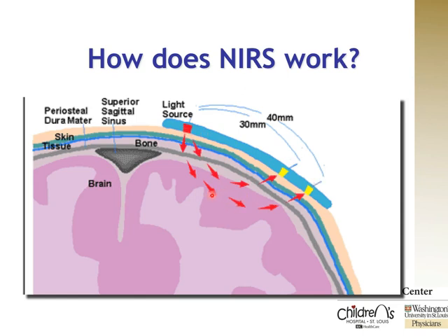And since we're really interested in the oxygen saturation of the tissue deep in the middle of the area under the probe, and not so much interested in the oxygen saturation of the skin or the skull or the dura, the device subtracts the superficial sensor's reading from the deep sensor's reading, and so that leaves us with an estimate of tissue oxygen saturation at a point about 1 centimeter or 2 deep from the skin under that center part of the probe. And so that's how the system works to give us that tissue oxygen saturation.